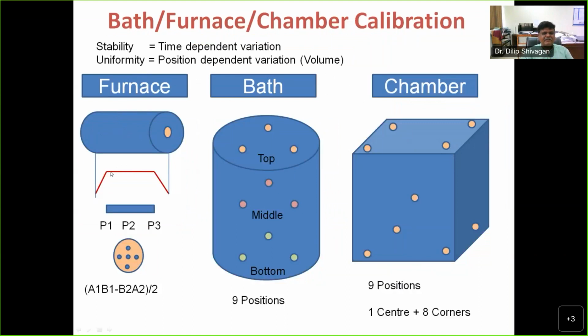This type of stable plateau you get between say middle 60 or 85% zone, and there you measure the stability and uniformity. Always put your standard and use it in that range only, never at the edge locations where you have the losses.